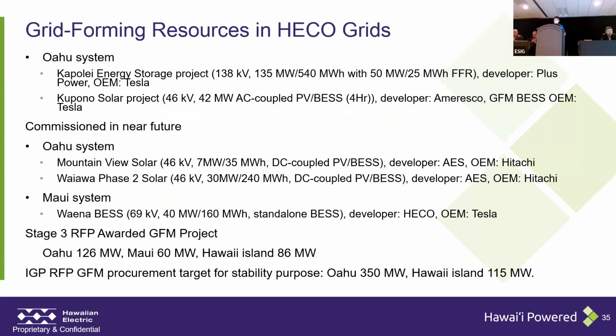Regarding the grid forming projects, I think everybody knows that we have transmission level interconnected grid forming projects. So the Kapolei Energy Storage project, 138 kV interconnection. It is a 135 megawatt 4-hour regular time shift battery, and then there's another 50 megawatt 0.5-hour duration fast frequency response unit integrated inside the facility, and the owner or developer is Plus Power and the OEM is Tesla.